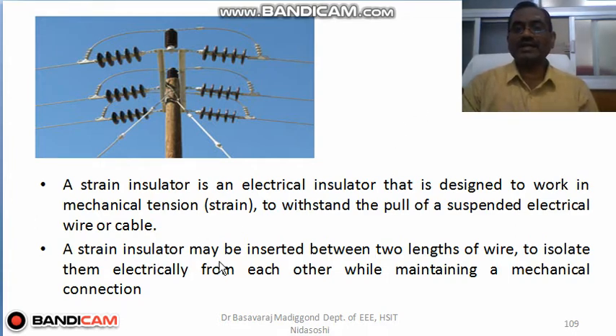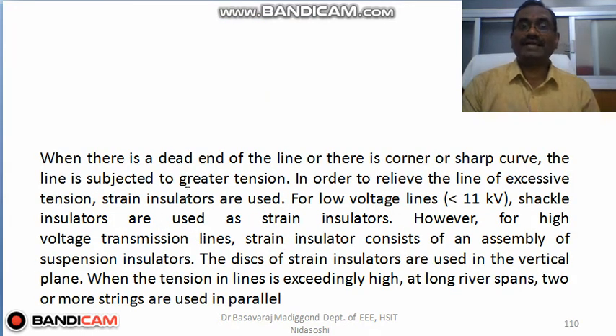A strain insulator may be inserted between two lengths of a wire. This is one length of a wire and this is another length of a wire. So this is inserted between the two lengths of a wire to isolate them electrically from each other while maintaining a mechanical connection. Okay. When there is a dead end of the line or there is a corner or sharp curve, the line is subjected to greater tension. In order to relieve the line of excessive tension, strain insulators are used.